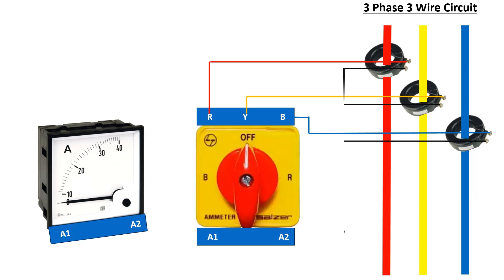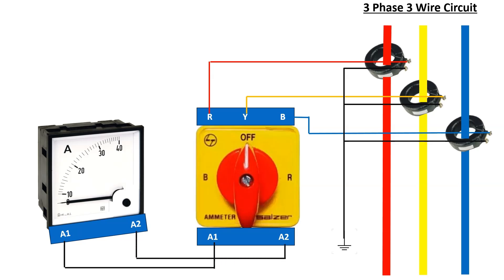It is important to note that all the current transformer other terminals are to be shorted to each other and connected to ground. Now, we will connect the A1 terminal of the ammeter and selector switch to each other. Next, we will connect the A2 terminal of the ammeter and selector switch, and connect the same wire to the CT common terminal which has been grounded.